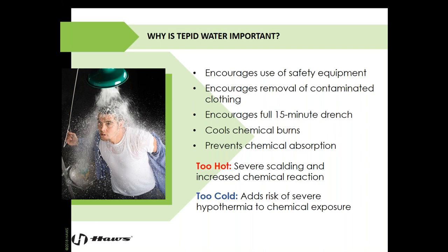Tepid water cools chemical burns. If we're providing really hot water coming out of this emergency equipment, it can have some negative effects on the chemicals that are already on your skin. So focusing on like an 85-degree number for that temperature of water coming out of the equipment is really important because it's going to cool that chemical and prevent more pain for the victim. It prevents chemical absorption. It closes the pores on our skin rather than opening them when we have scalding hot water coming out of the equipment.